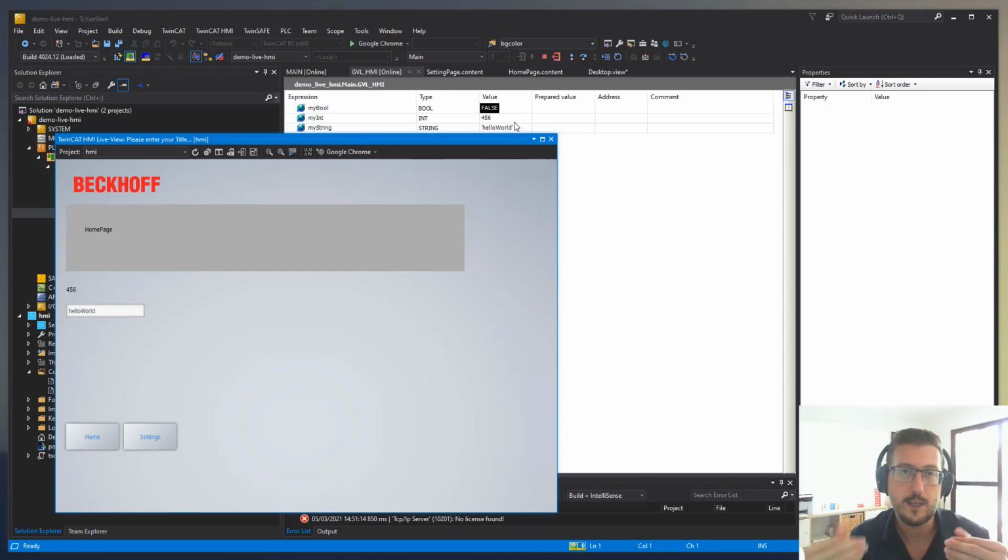So this is hopefully explaining to you that everything is based on binding, and just be wary that sometimes things aren't what they seem. Typically, the binding will be sufficient for what you're after, but some controls aren't sure what's the best way to bind, and therefore they take the safest option. Just remember, double click on the binding itself and you get some extra options, where you can say whether it's on change, whether it's polled, and also whether it's one or two-way binding.